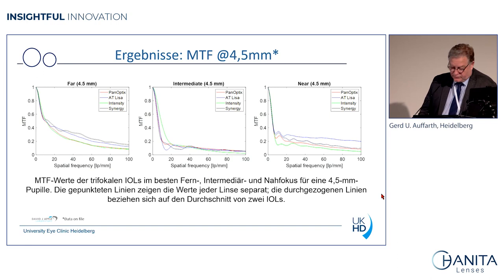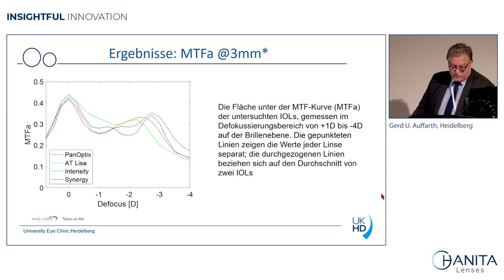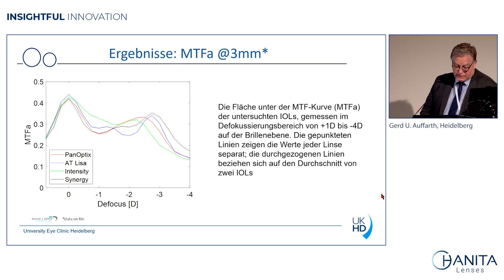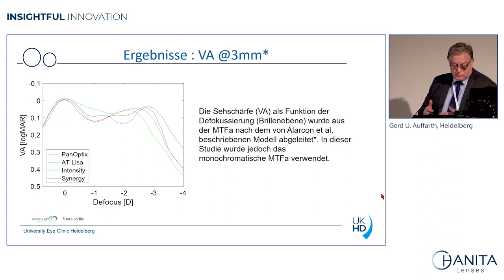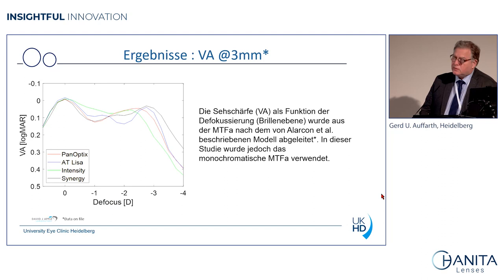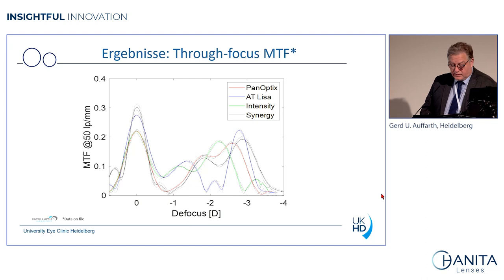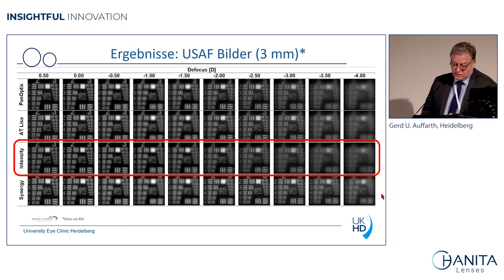With a larger pupil there is a little more light distribution. We can also correlate MTF with defocus: looking at the minus-1 D range, roughly minus 0.75 to minus 1.25, the green line representing the Intensity is way above the other lenses. Between minus 2 and minus 3 diopters they are all the same. Correlating defocus with simulated visual acuity confirms the same superiority of the Intensity in that specific intermediate area. In the through-focus MTF you can also see that some lenses behave more bifocally and some more trifocally, while the Intensity is very similar to the others overall.